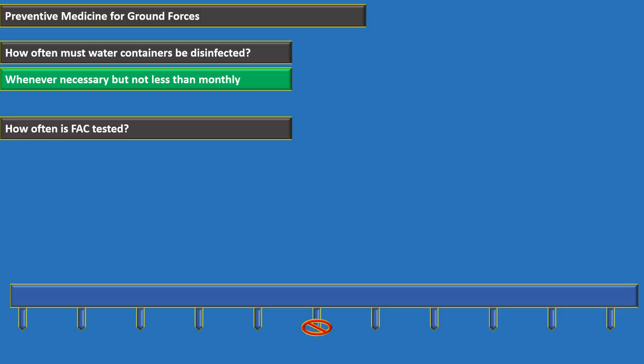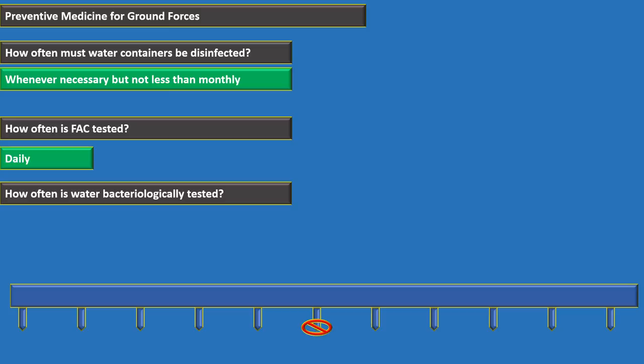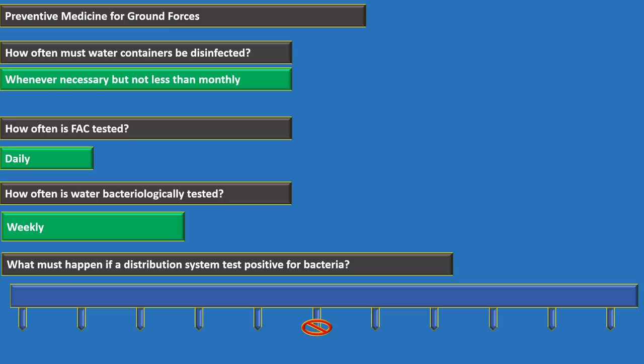Water is tested for bacteria weekly. If a distribution system tests positive for bacteria, retest at the positive location after troubleshooting and disinfection, then retest five outlets upstream and five outlets downstream.